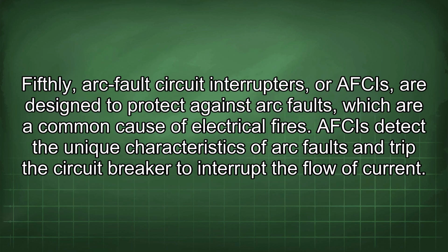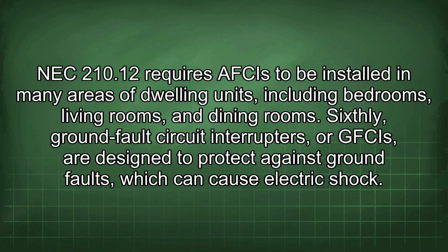Fifthly, arc fault circuit interrupters, or AFCIs, are designed to protect against arc faults, which are a common cause of electrical fires. AFCIs detect the unique characteristics of arc faults and trip the circuit breaker to interrupt the flow of current. NEC 210.12 requires AFCIs to be installed in many areas of dwelling units, including bedrooms, living rooms, and dining rooms.